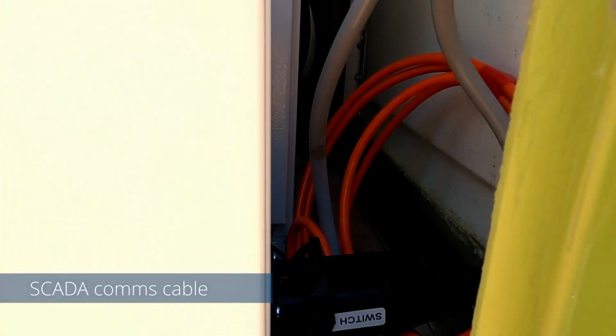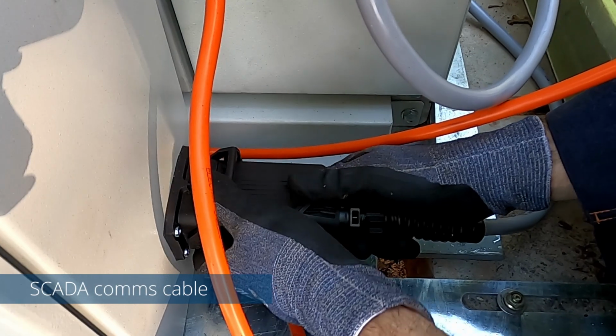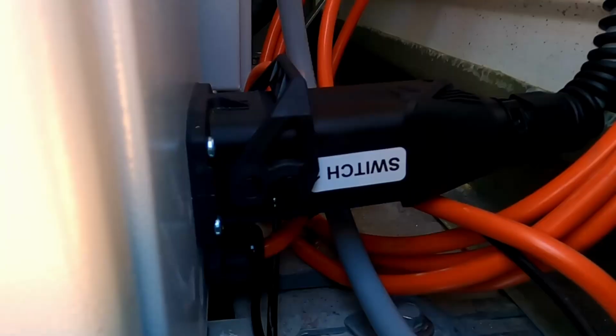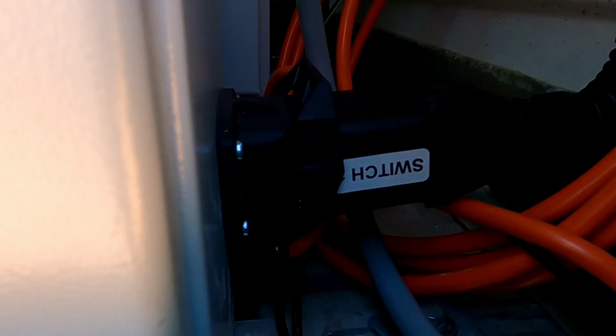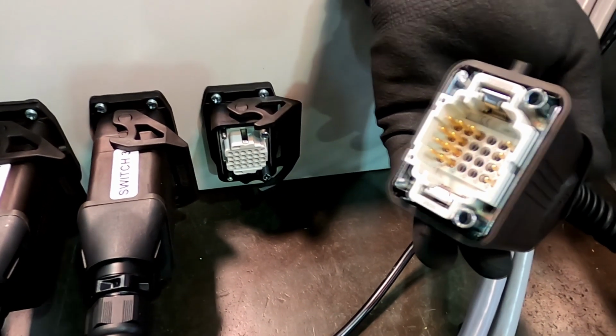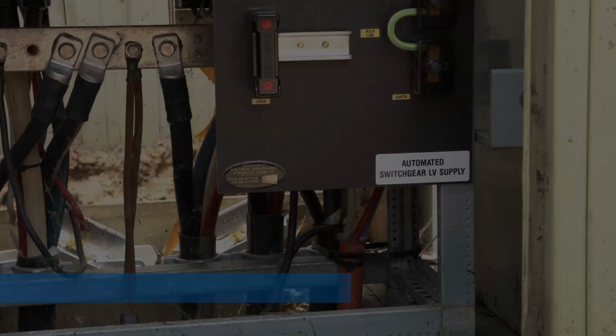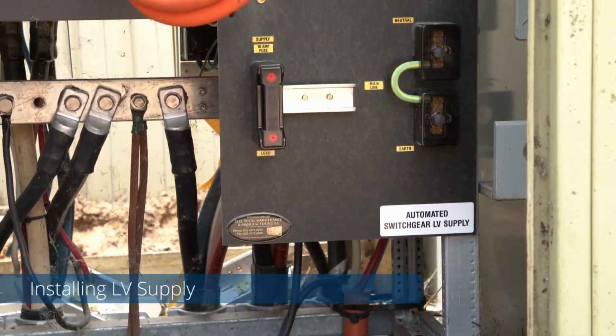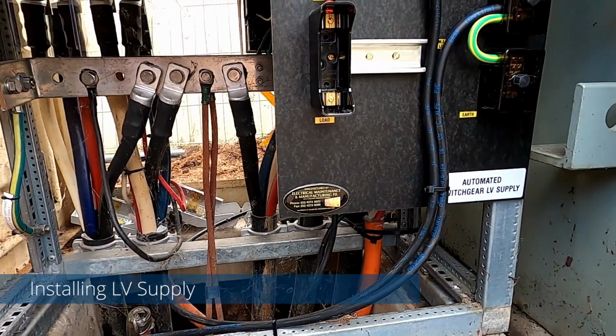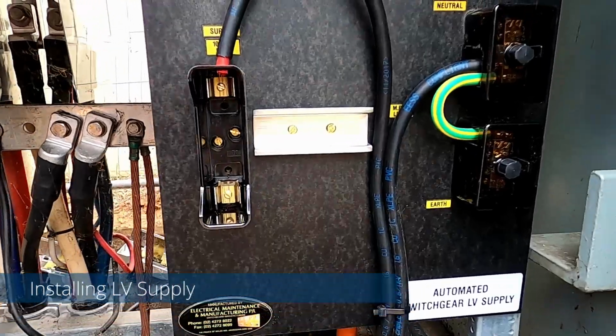Insert the SCADA communication cable plug into its socket and secure the catch in place. There will be one cable per motorized switch. Note that each plug will only fit the socket with a correct pin configuration. Find a suitable location for the switchgear LV supply panel and fix in place to the framework.